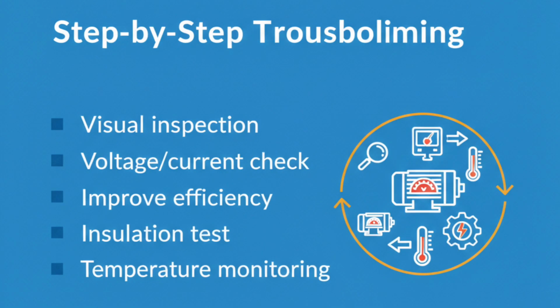A systematic troubleshooting approach should always be followed. Start with a visual inspection for burnt smell, discoloration, loose wires, dust accumulation, or oil leakage. Measure voltage and current in all three phases to check balance. Perform insulation resistance testing before energizing after repairs. Check bearing temperature and vibration. Confirm that the driven load is not exceeding rated value.